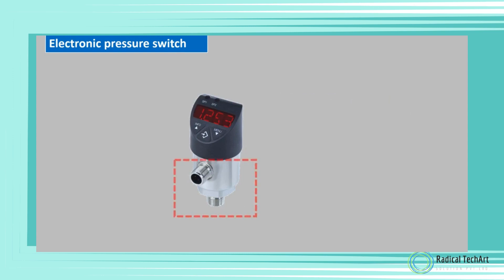Electronic pressure switch: An electronic pressure switch is a pressure sensing instrument which uses a pressure sensor and conditioning electronics which provides a switch output that is open or closed circuit using either a relay or NPN or PNP output. Most electronic pressure switches have analog capabilities, this means they are not limited to open or closed position but are also capable of sending a continuous variable signal.